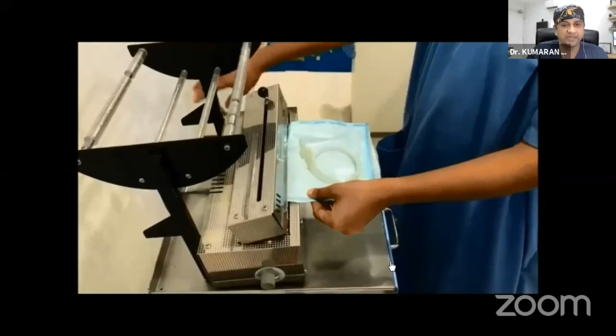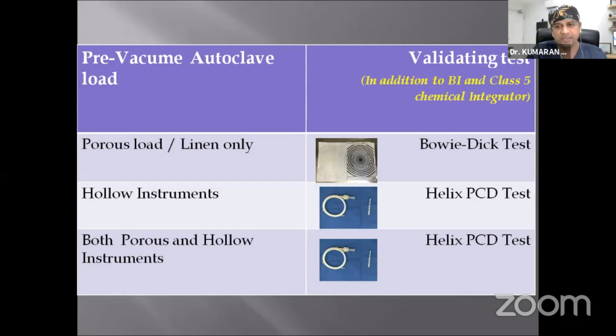Make sure you use a medical grade sealant to close this, which is actually 3 centimeters in length, and then it is autoclaved. So this is the class 6 indicator, how this should be used. If you're using only porous or linen, use the Bowie-Dick test. Hollow instrument and porous instrument, use the PCD test.